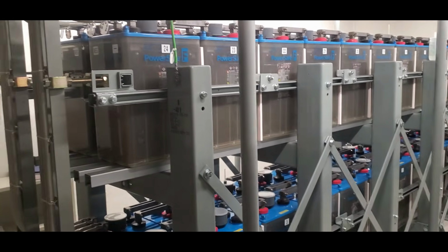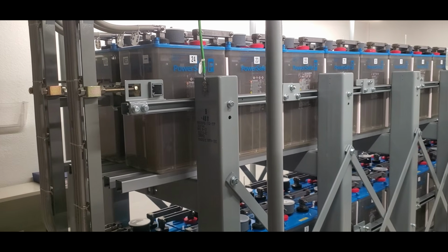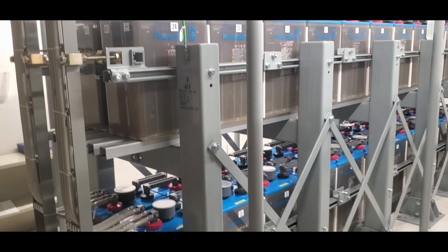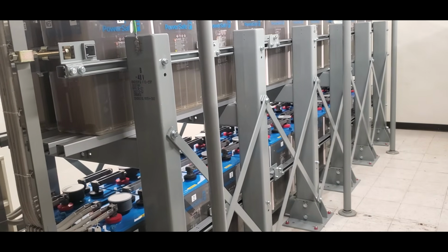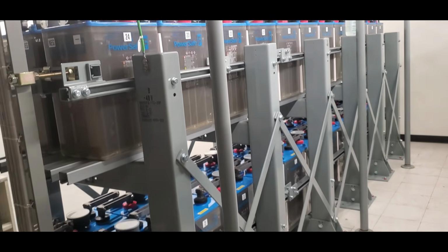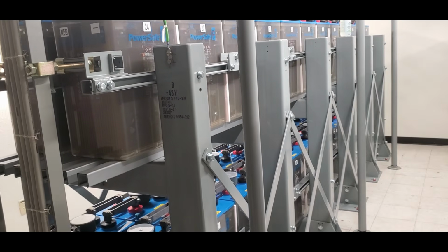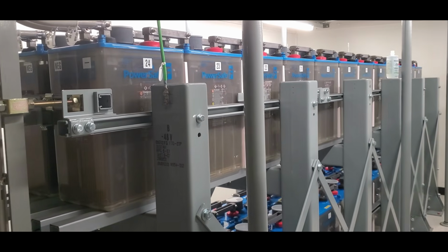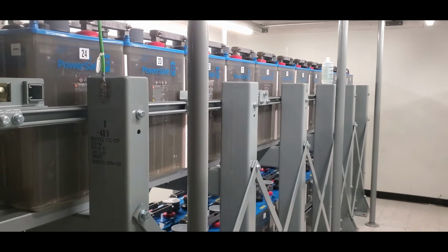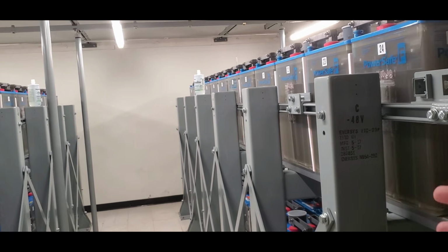So what happens is if we lose power to this building, then the equipment stays running, it never shuts down, just because the batteries take over and fill in that gap between the generator starting and transferring over and the commercial power taking over. So with the DC plant, the equipment never loses power. It's always going to have power somehow. That is why, like, the old telephones always had power, because there were batteries here.